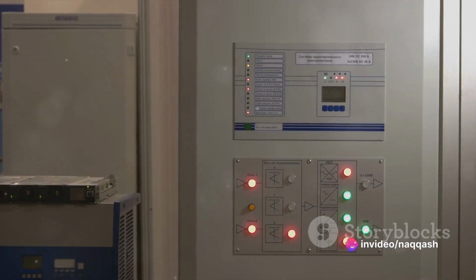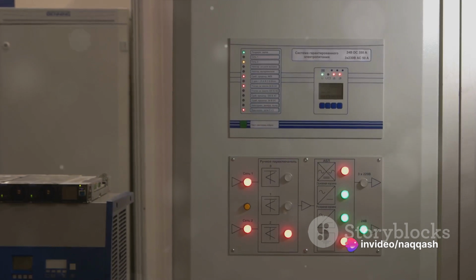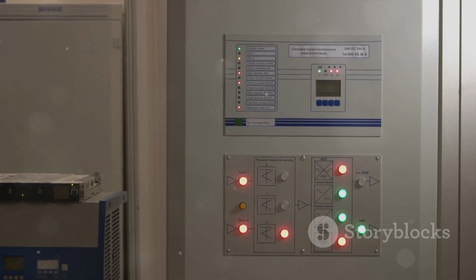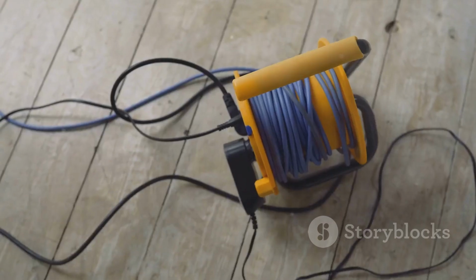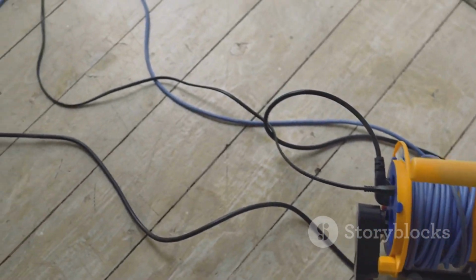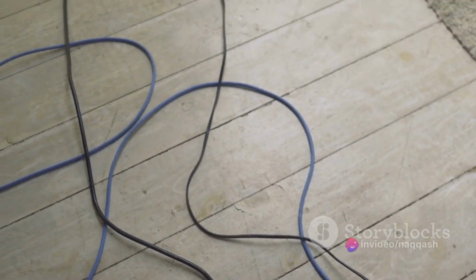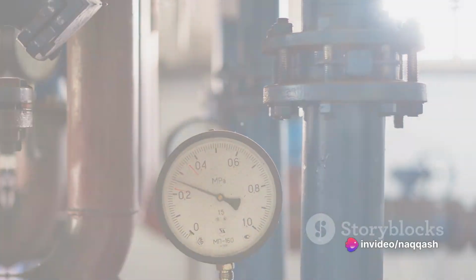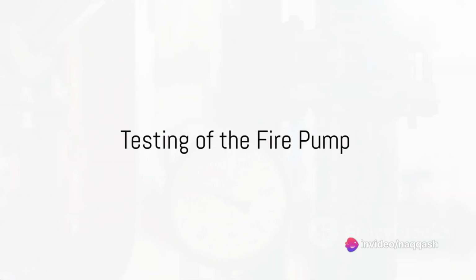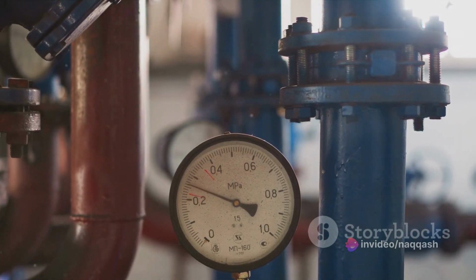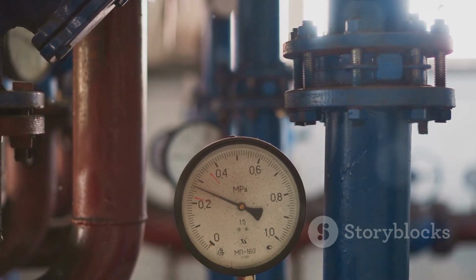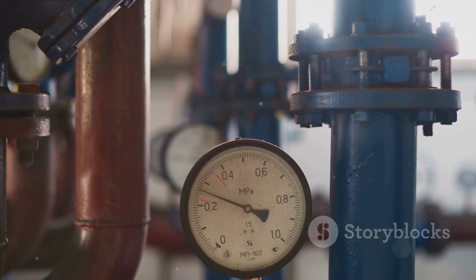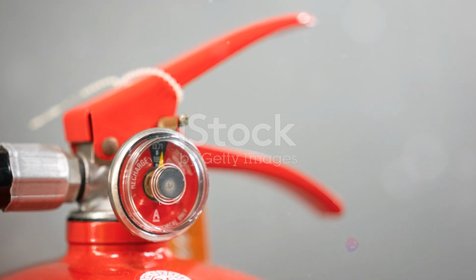In most cases, a fire pump requires a dedicated power source to ensure it can operate even if the main power is lost. The pump should be connected to the power supply using correctly sized cables and circuit breakers. The final step in the installation process is testing. The pump should be run under full load conditions to verify its performance. This includes checking the pump's pressure, flow, and power consumption.